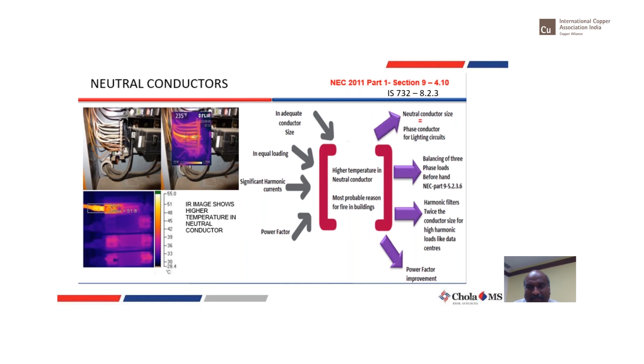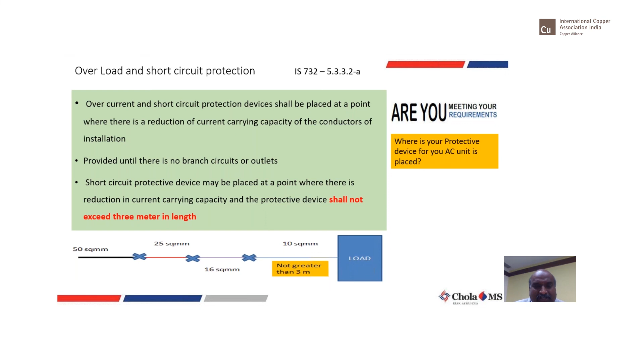And one more thing: whenever you have a large size, say 50 square mm to 25 square mm, 25 to 16 or 16 to 10, whenever there is a change in the size of the cable, say you are running a 50 square mm cable from a plant room to some DB, and there you are terminating it, not even on a breaker, but on a bus bar. From there again you are taking a 25, from there you are again taking a 16. Please ensure that wherever there is a change in the cable sizing, you always have some protection device. So when there is a cable change from 50 to 25 square mm, don't put a joint just like that. Please have proper tripping devices, and please ensure that the last tripping device connected to the load is at a distance of not more than 3 meters.